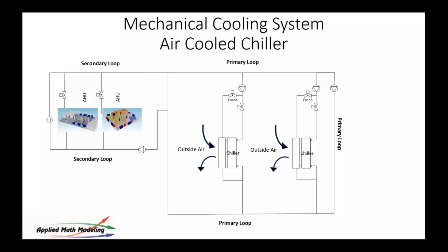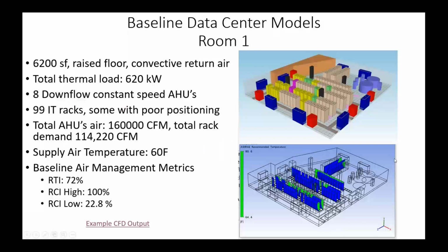Two chillers are there for N+1, typically two pumps. Everything has doubles on it for redundancy. Room 1 here, pretty straightforward. I already mentioned to you, we assume the air handlers are running full tilt because that's not unusual for older systems. Total rack demand 114.